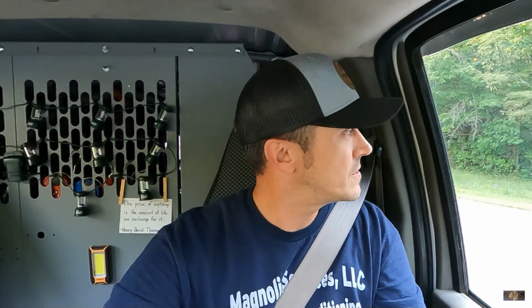Typically that unit runs low superheat because it's not moving enough air. Seven, eight, nine degrees is about the best it does, normally running lower than that depending on conditions. Even if it's calling for more superheat, it's not going to do it. It's a 2.5 ton unit on 1.5 tons of ductwork, which is crazy. The one saving grace is the 20 by 25 return it sits on top of, so it's got plenty of return capacity, it's just the supply is super restricted. So it is what it is.